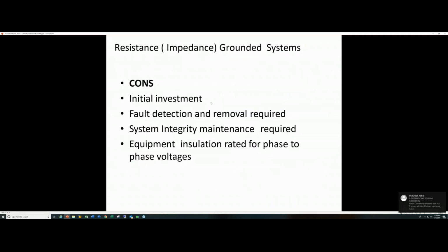Well, your initial investment is higher, of course, because you have to purchase the HRG and you have to install the HRG on either new equipment or on retros that you're doing. Fault detection and removal is required. As I said, once the fault hits, you need to go after that first phase to ground fault, because when a second fault happens, it's really catastrophic at that point. It's just like if you had a solidly grounded, or even worse.